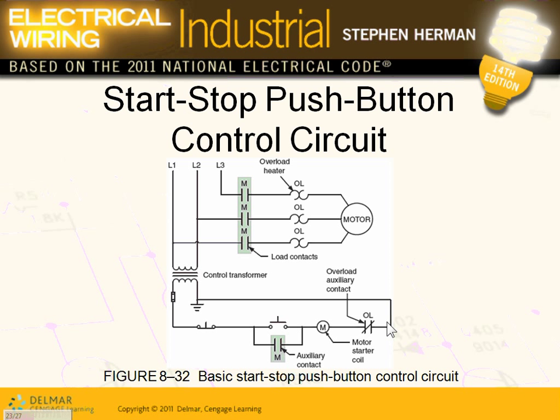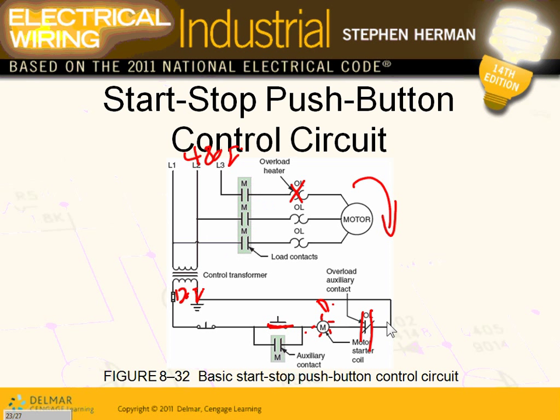If you leave Dunwoody without knowing how to read and understand this, you're doing yourself a disservice. Magnetic starters — here's your start button. When you push start, let's say this is a 480 volt system, you energize the coil. When the coil is energized, it drives the contacts shut. My motor is running. If an overload opens this contact, it will de-energize the coil and the contacts will open again. That's the basic magnetic starter control and power circuit.